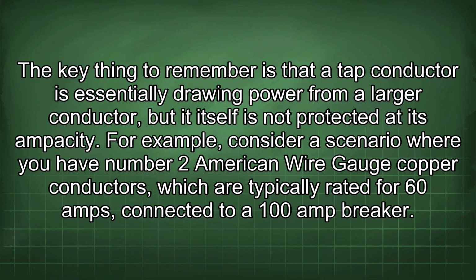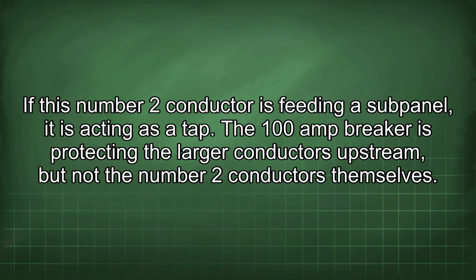For example, consider a scenario where you have number 2 American wire gauge copper conductors, which are typically rated for 60 amps, connected to a 100 amp breaker. If this number 2 conductor is feeding a subpanel, it is acting as a tap. A 100 amp breaker is protecting the larger conductors upstream, but not the number 2 conductors themselves.